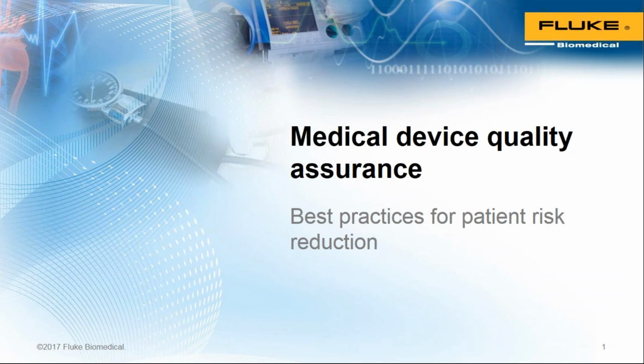There's another test that you do during electrical leakage current testing, and that's applied part, mains on applied part. And that tests the isolation of the medical device and the patient connections in particular. So these tests are designed to evaluate different pieces of the puzzle about the electrical distribution systems, the safety of the design of the product, and in fact the safety in managing the risk of the patient by making sure that there is an appropriate and low resistance pathway back to ground for all electrical current flowing on the device.